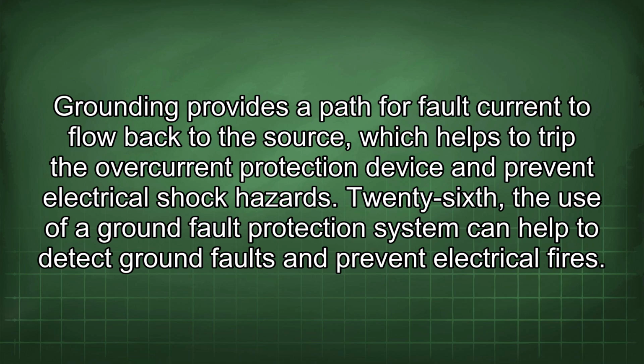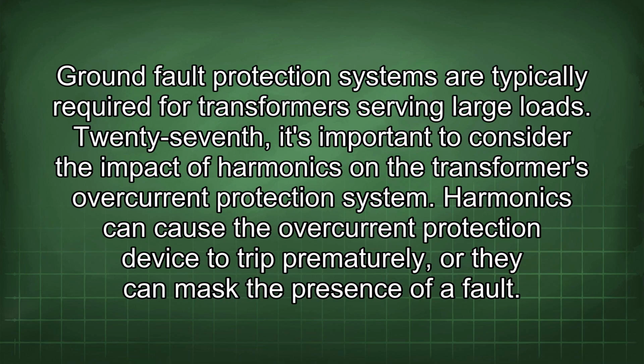26th, the use of a ground fault protection system can help to detect ground faults and prevent electrical fires. Ground fault protection systems are typically required for transformers serving large loads. 27th, it's important to consider the impact of harmonics on the transformer's overcurrent protection system. Harmonics can cause the overcurrent protection device to trip prematurely, or they can mask the presence of a fault.